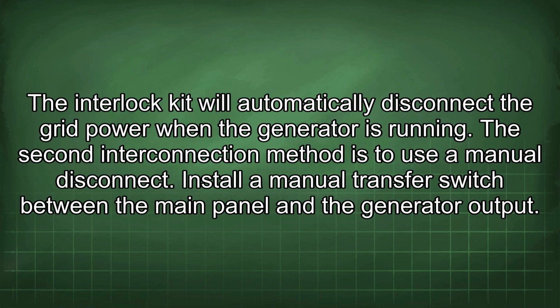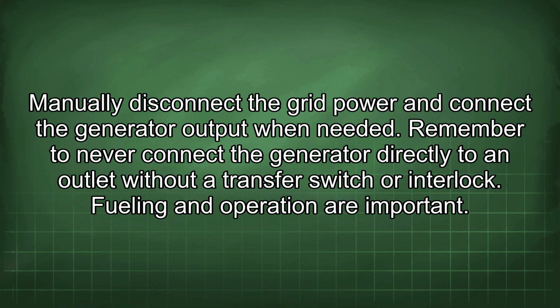The second interconnection method is to use a manual disconnect. Install a manual transfer switch between the main panel and the generator output. Manually disconnect the grid power and connect the generator output when needed. Remember to never connect the generator directly to an outlet without a transfer switch or interlock.